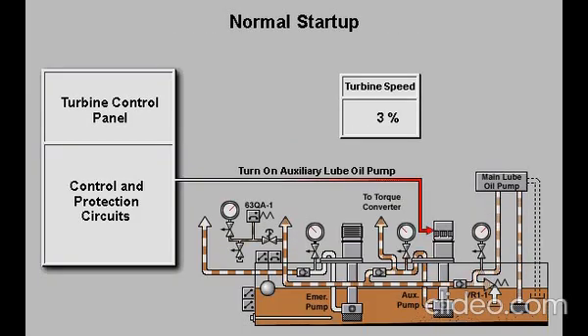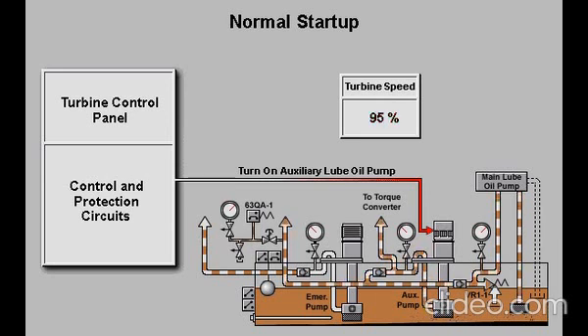While the turbine is starting, the shaft-driven main lube oil pump is at a speed insufficient to develop operating pressure. As long as AC power is available, the auxiliary pump supplies oil throughout the lube oil system until the turbine reaches approximately 95% speed. At this point, the control system shuts off the auxiliary lube oil pump and lube oil pressure is maintained by the main lube oil pump.